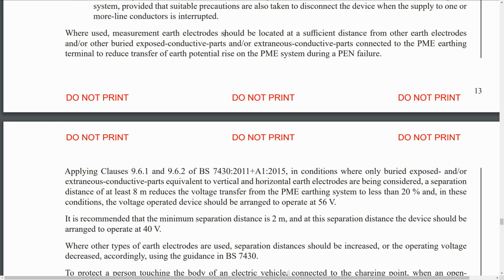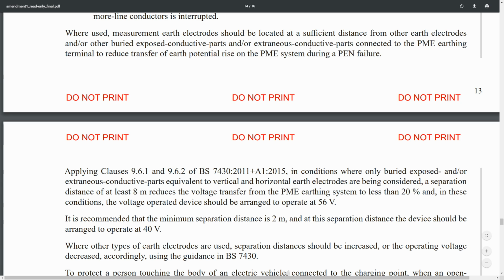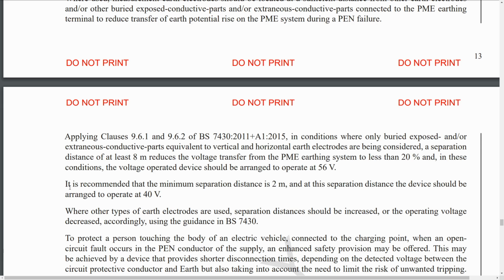Measurement earth electrodes should be located at sufficient distance from other earth electrodes and other buried exposed conductive parts and extraneous conductive parts. As I said earlier, if it's not, and a fault occurs, then that voltage can be transferred onto the electrode, which completely negates the point of having it. As it's got down here, it's recommended the minimum separation distance is 2 meters, and that would be, if you say a more traditional earth electrode of say 1 meter depth, it would need to be 2 meters away, say twice the distance.